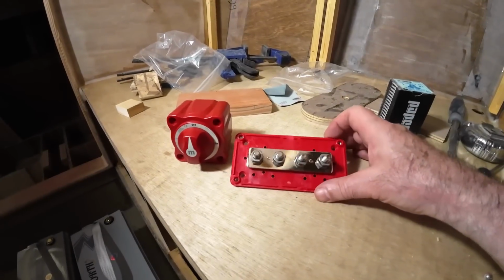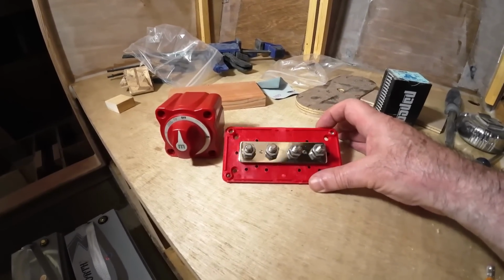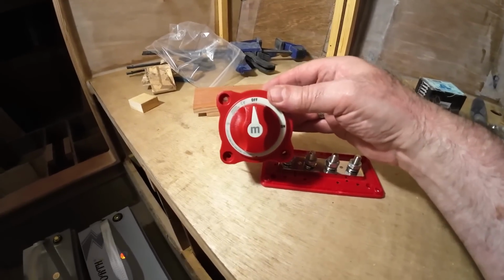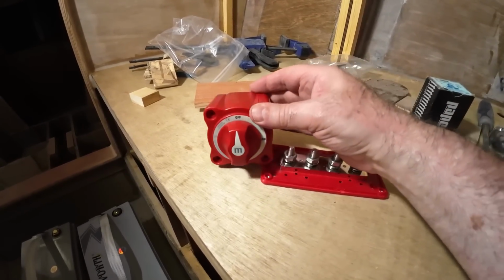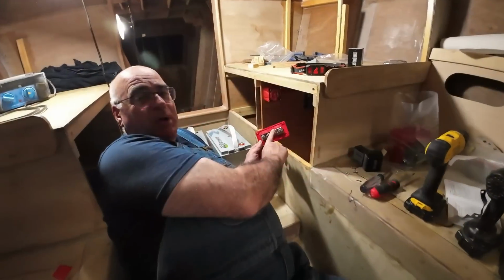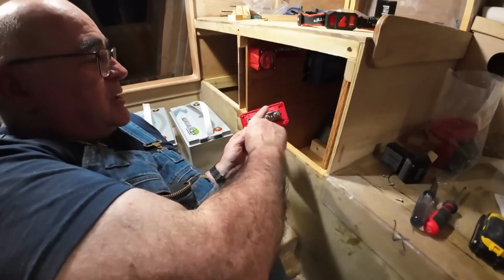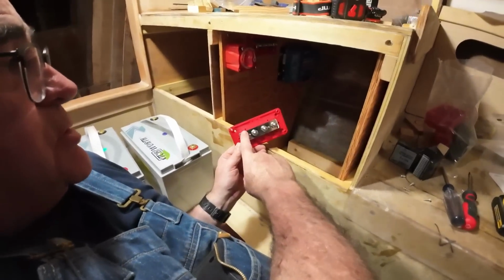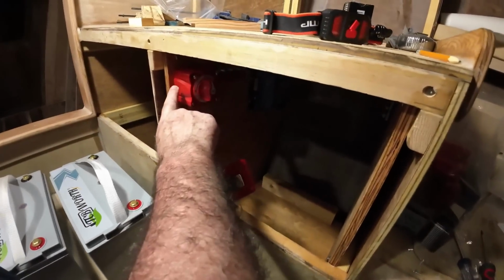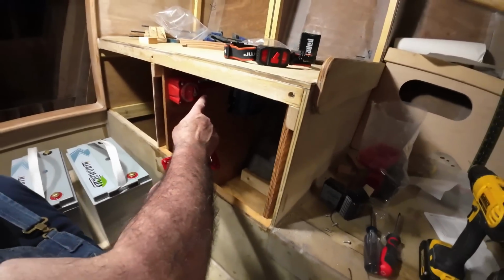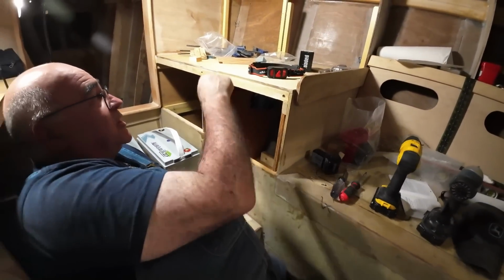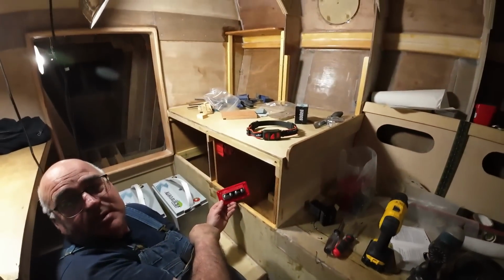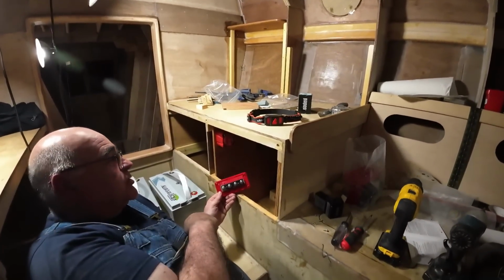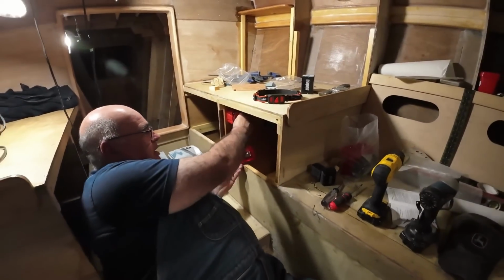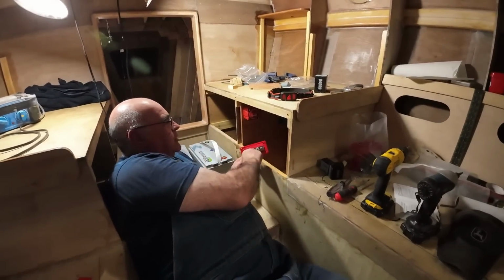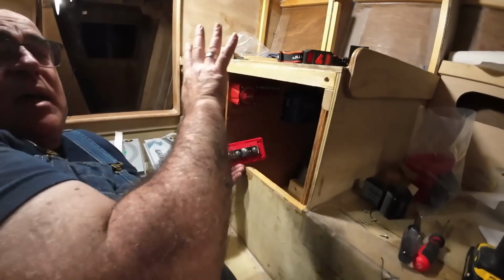The next components to be installed are the DC positive bus bar and the system on-off control switch. The two positive DC bus bars - the MPPT will come to this, from this will go to the switch, which from the switch will go to the main DC positive bus bar, which will feed up to your panel and switches for your loads up there, where you'll be able to control everything. This switch here, when off, shuts down your whole load system.